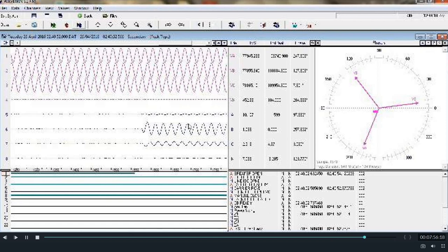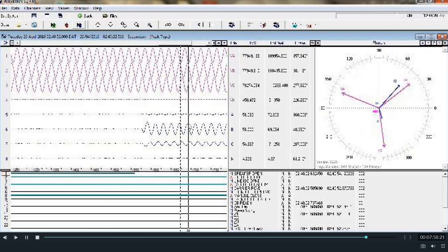So where has this current come from? This is because of auto reclose. Here we can observe that after around 1500 milliseconds the line was auto reclosed, and because of the auto reclose the line was again closed. From the remote end, we earlier said that the line didn't trip, so from this end when the line was closed again, current started flowing. That's why the current waveform has come in the DR file after 1500 milliseconds.